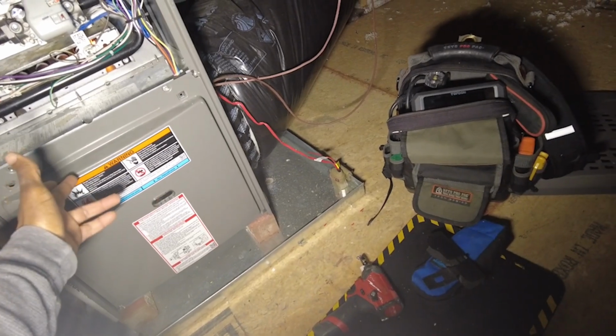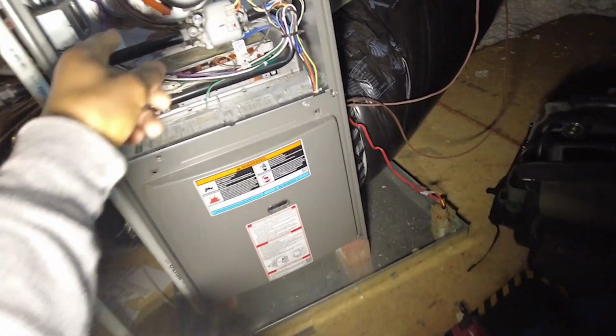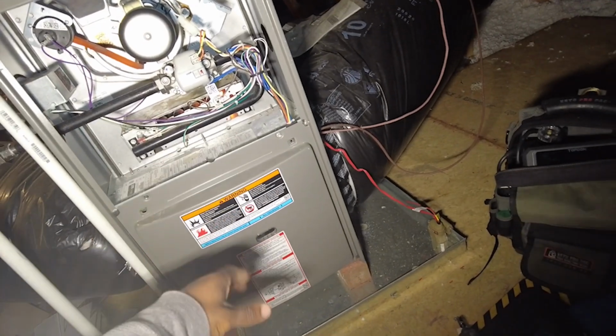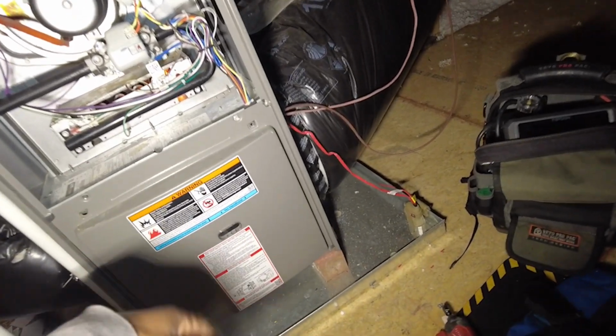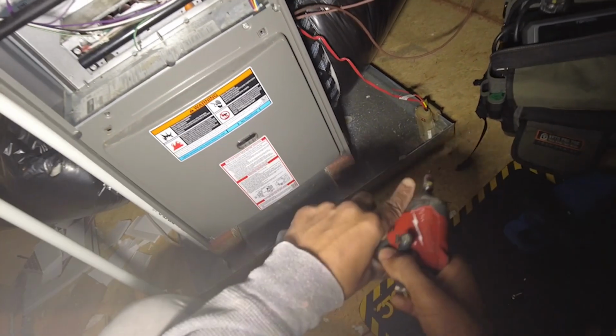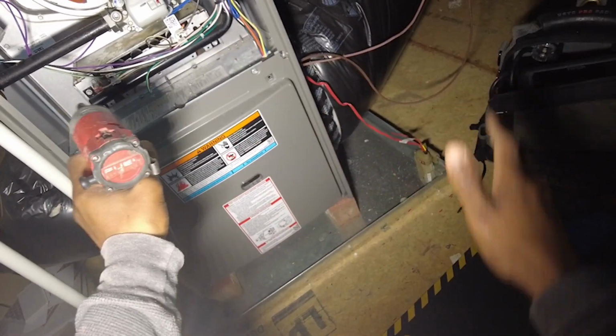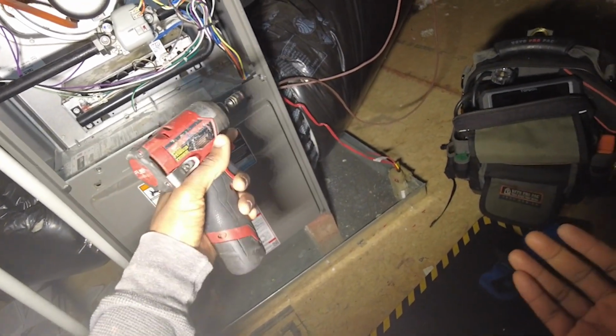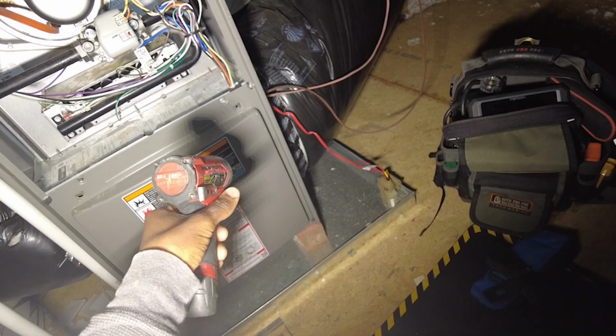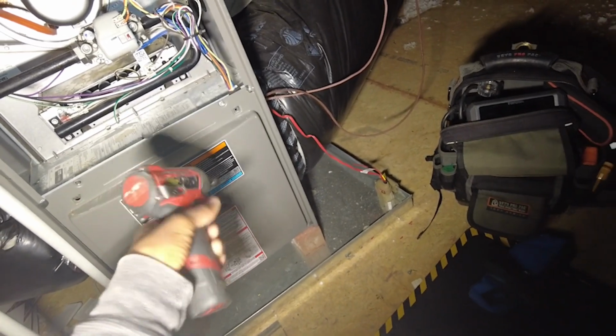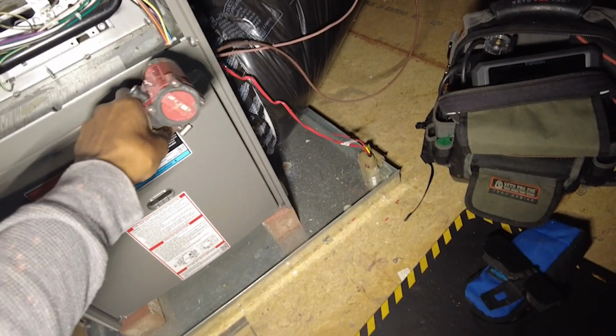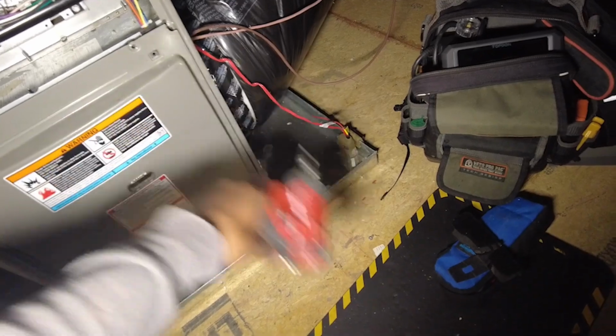You hear that blower still running? The inducer's still running, as you can see. What that's trying to do is basically cool off the heat exchanger before the system turns off. Because if your system cuts off, all the blower and all the inducer cuts off, that heat exchanger is going to still be hot as crap, and it could potentially cause stress cracks and things like that. So I let that run for a bit, just cool it down. Now we let it shut off.